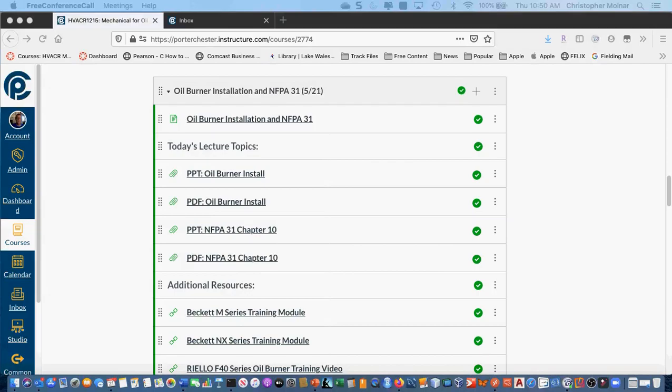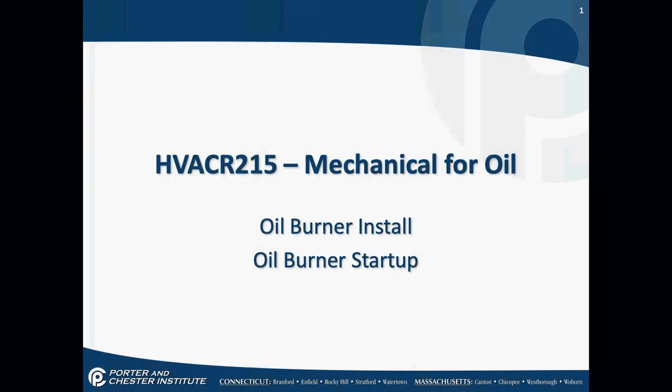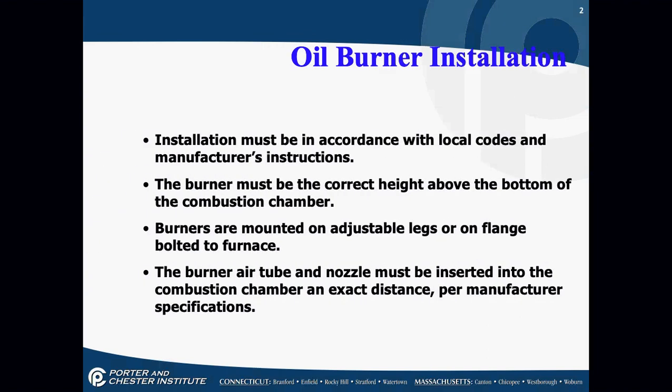Let's talk about burner installs first. When we install a burner, we have to install according to local codes and manufacturer's instructions — manufacturer instructions cannot be lesser than local codes. The burner must be the correct height above the bottom of the combustion chamber, and burners are mounted on adjustable legs or on a flange bolted to the furnace; they cannot move around or fall out.